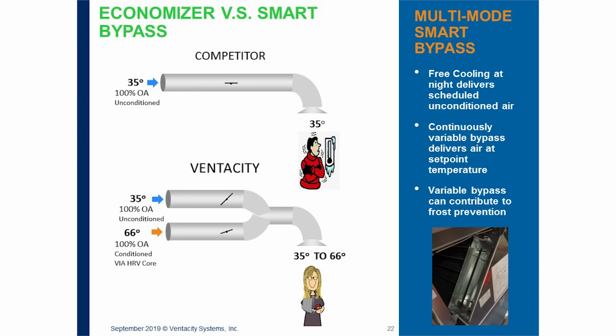Versus an economizer, which is on a rooftop unit. Again, the economizer will open and allow for fresh air to come in, but because it's not going through a ventilation system like this, it's going right into the ductwork and you have to post-heat and post-cool that. So you're using a lot of energy in order to do that.